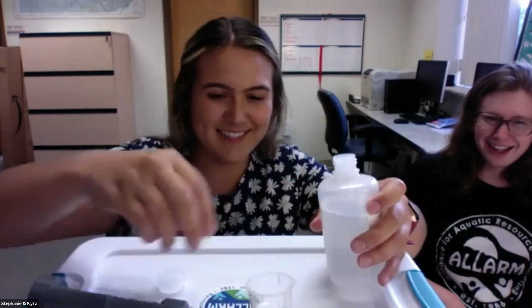Yes, perfect. I'm just joshing with you. Anyway, so we're pouring out that approximately 12 mils into the vial, just enough to cover those electrodes. And then the second you've got that in there, put that conductivity meter in there, start swirling around, and let your reading stabilize. You do need a little more, don't you? I know. See, that's what I get for being like, oh, you poured out too much the first time, then you didn't pour out enough this time. But you all will find that sweet spot with the calibration vial and making sure your electrodes are covered.